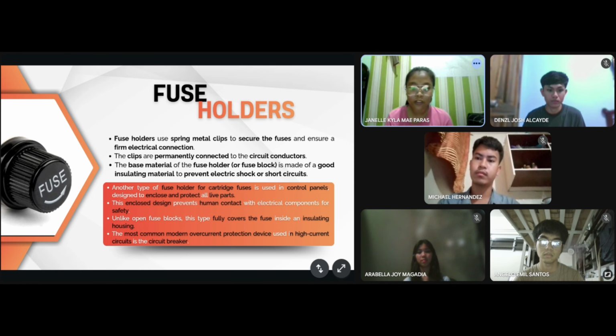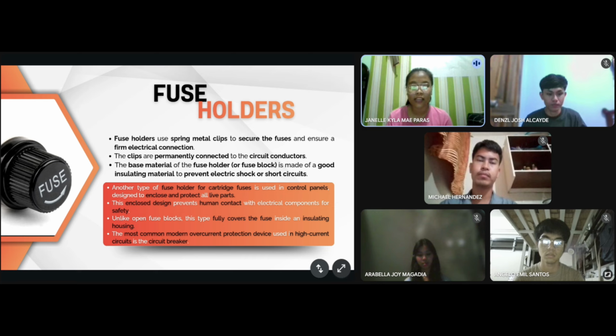Another type of fuse holder for cartridge fuses is commonly used in control panels and is designed to enclose and protect all the parts. This enclosed design prevents human contact with electrical components, ensuring safety. Unlike open fuse blocks, this type completely covers the fuse inside an insulating housing. In modern electrical systems, the most common overcurrent protection device used in high current circuits is the circuit breaker.